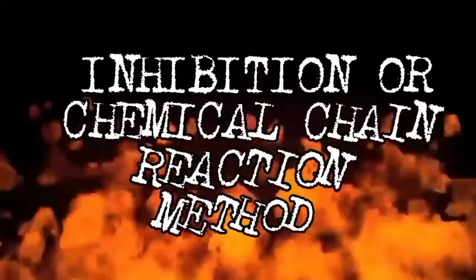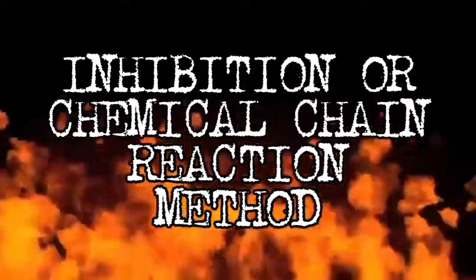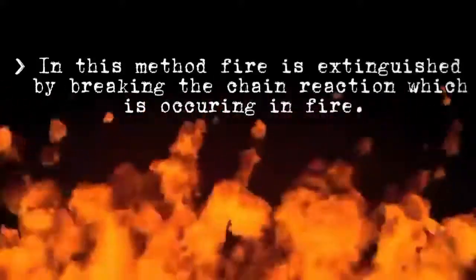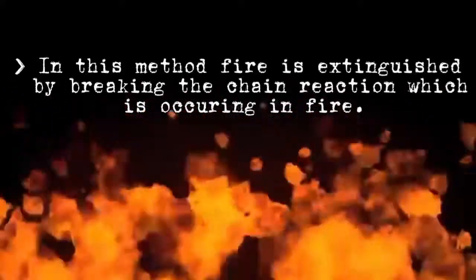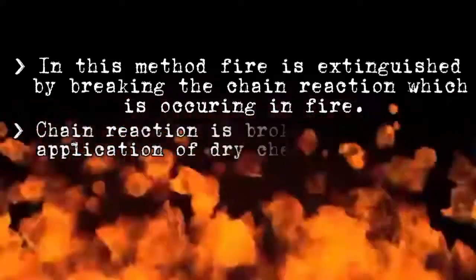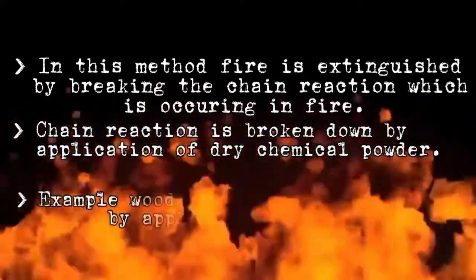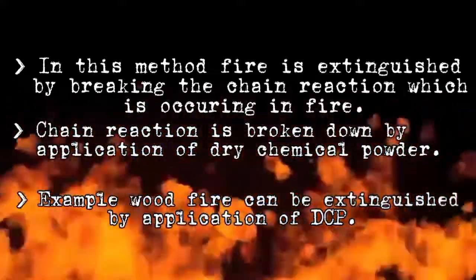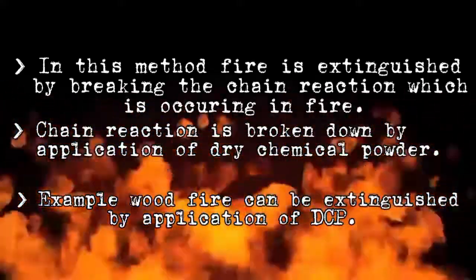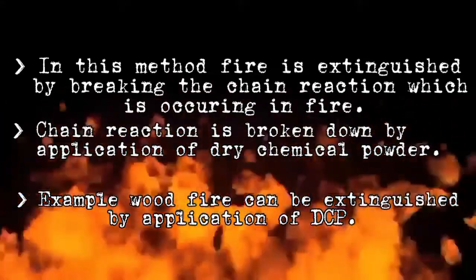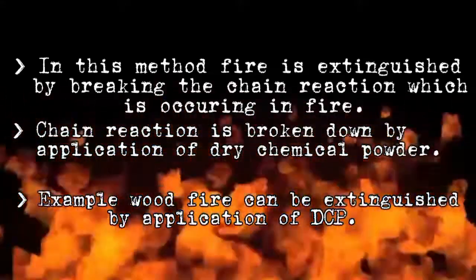And the last method is inhibition or chemical chain reaction method. In this method, fire is extinguished by breaking the chain reaction which is occurring in fire. The chain reaction is broken down by application of dry chemical powder. Example is wood fire can be extinguished by application of DCP or dry chemical powder.